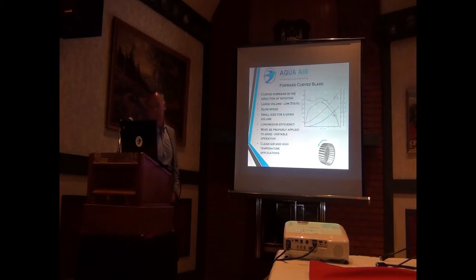So when you talk about forward curve blade fans, this is a fan curve. I don't know how familiar people are with a fan curve, but it measures static pressure, CFM, and horsepower. The main driving factor on a fan is the static pressure. With forward curve fans, we talked about blades curved forward in the direction of rotation of the air: large volume, low static pressure, slower speeds, small size for a given volume, lower to medium efficiency, and they must be properly applied to avoid unstable operation. This is very important when you're selecting a fan. This green line here curves up to the peak, down, and then back up again. You want to be no more than about 90% of your maximum static pressure on this side of that curve.